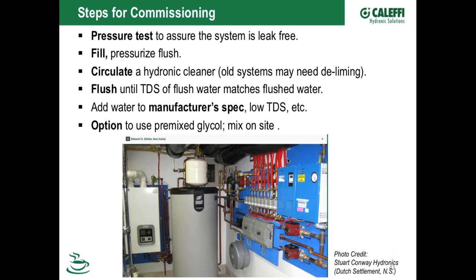Yes and no. You can blend different propylene glycols (PGs) without a problem. The issue is if somebody put an ethylene glycol (EG) in there before you, and now you mix another PG glycol with it. The two will mix and act as antifreeze fine, but you'll end up with an unknown toxicity, since EG has higher toxicity than PG. So you've got a bit of a witch's brew. If you don't know what's in there and want to do it right, you're probably going to have to drain it out and start over.